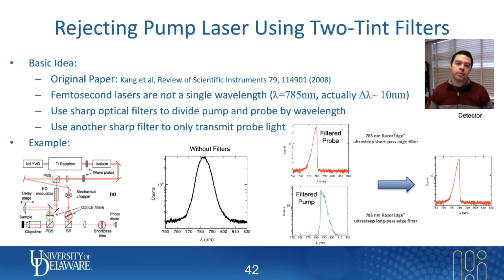So that is basically the strategy behind using two-tint filters, and it's quite effective for removing the portion that makes it through the polarizing beam splitter, and especially so whenever there's diffusely scattered light from the sample.